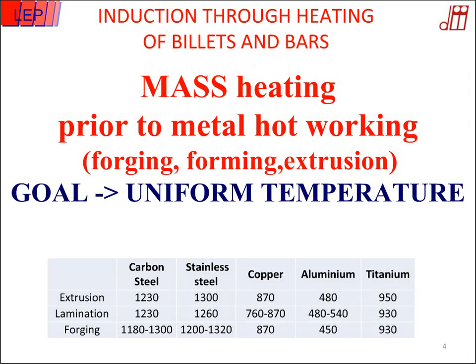Today, we will talk about the mass heating of metals — a thermal process that is required before hot working, mechanical working, like forging, forming, and extrusion. The main goal of this technology is to obtain a uniform temperature across the radius of the billet. Sometimes along the axis we are required to have a specific temperature distribution, but for today we can assume uniform temperature all along the mass of the billet.